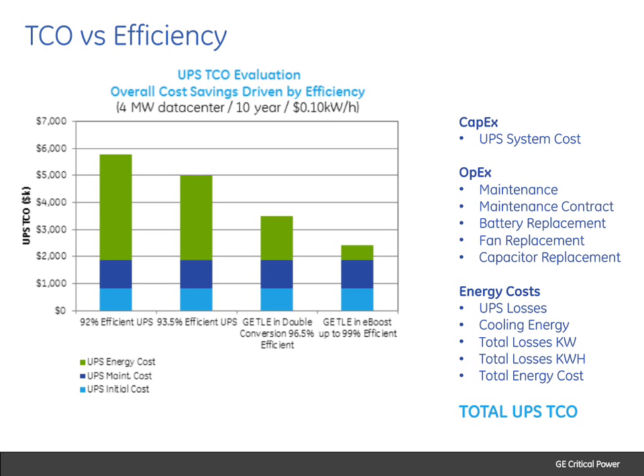So what it means is that if you start with a very inefficient UPS, like 92-93%, the energy consumption dominates the TCO model. If you keep going to the right and get up to 99%, where efficiency is very high and energy consumption cost is very low, then energy consumption becomes a smaller part of the TCO.